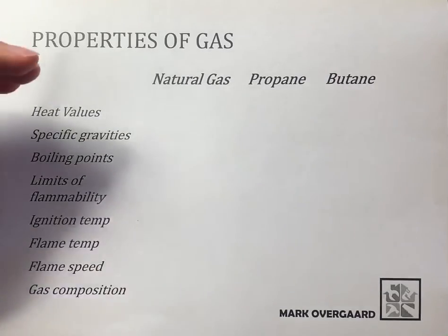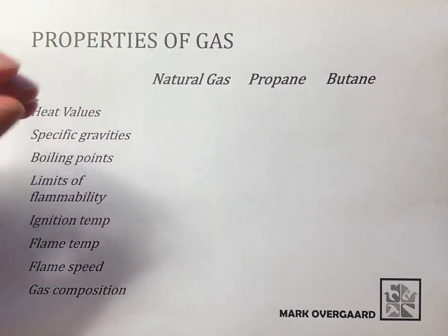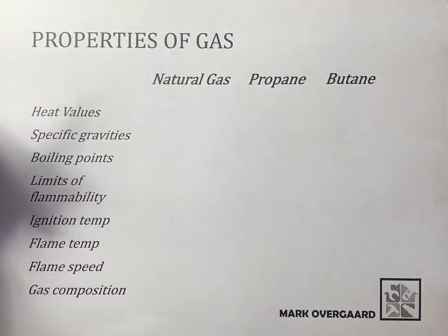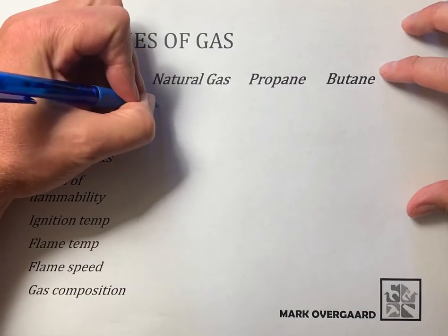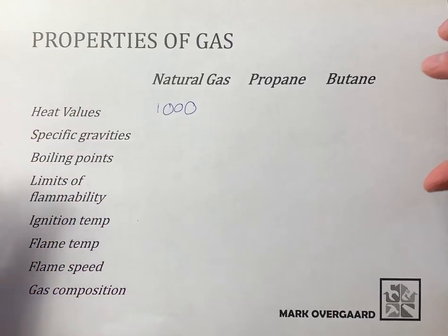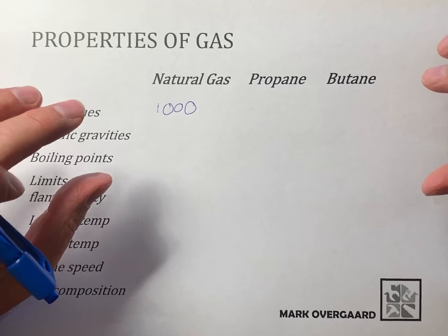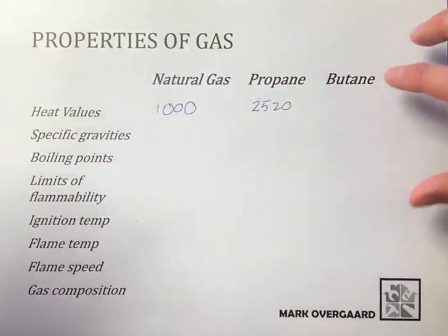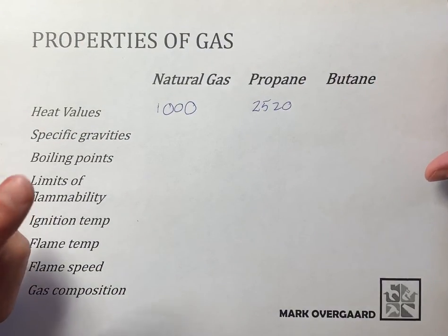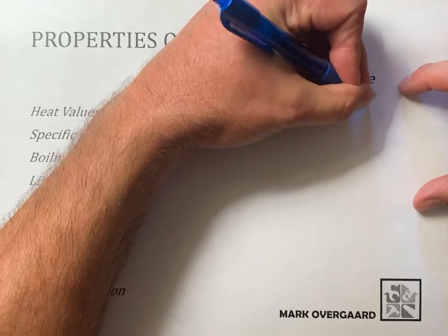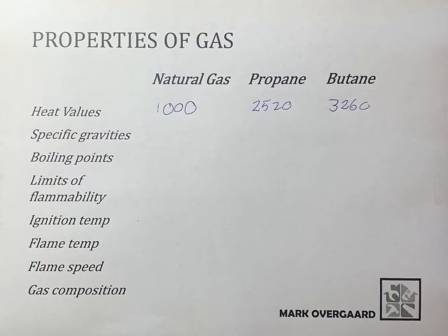Heat values — basically, if you take a cubic foot of either natural gas, propane, or butane and you burn it, how much heat energy do you get? We measure this in BTUs, or British Thermal Units. For natural gas, you get 1,000 BTUs per cubic foot. Propane is a little bit more — 2,520 BTUs per cubic foot. Butane is even a little more at 3,260 BTUs per cubic foot.